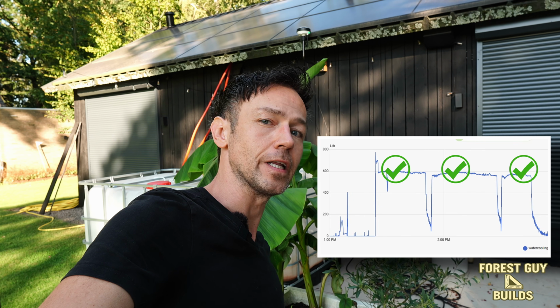If the flow of the small circulation pump drops below 70 liters an hour, the automation waits 30 seconds. If it's still below 70 liters per hour after those 30 seconds, it runs the groundwater pump for 3 minutes to fill the buffer. The flow then automatically returns to its configured level and the system continues running. That's basically a continuous little feedback loop, making sure there's always enough cooling water available.